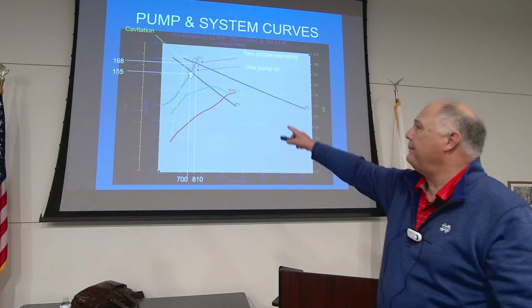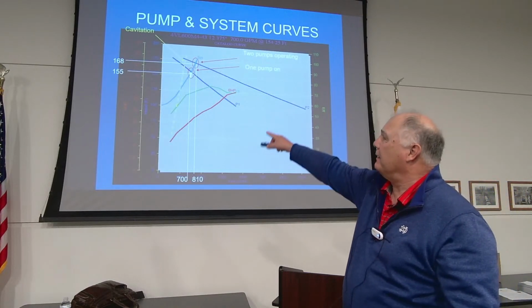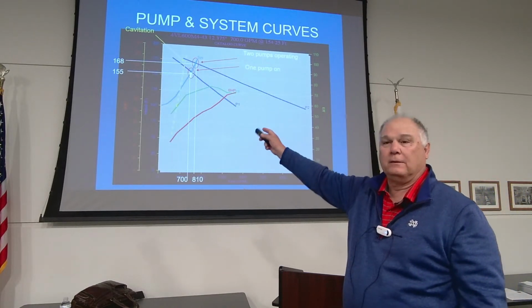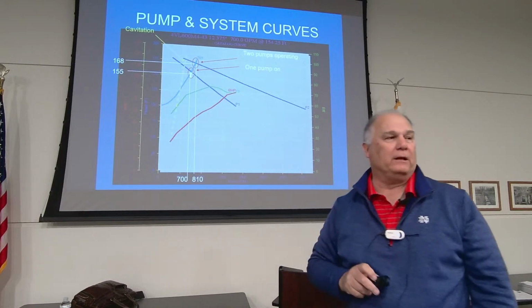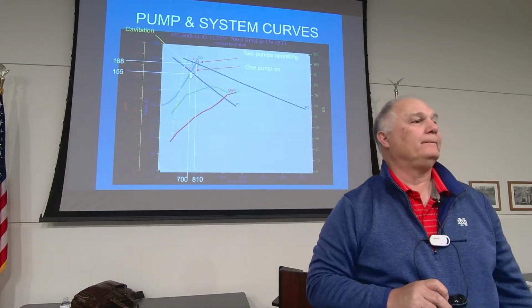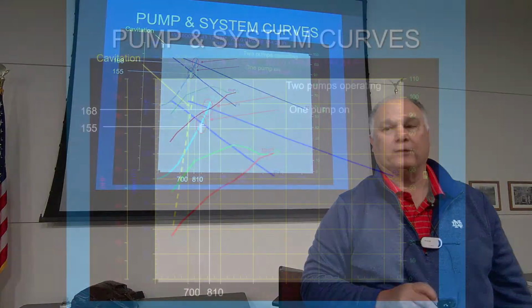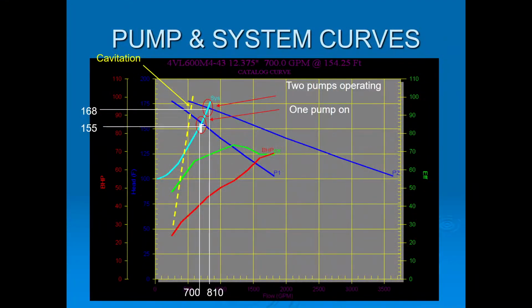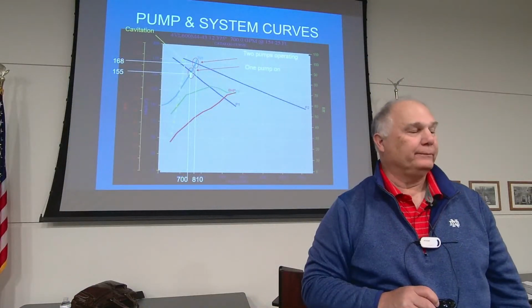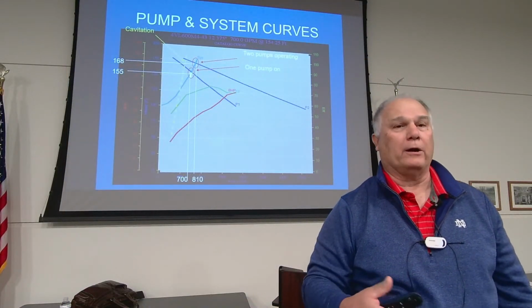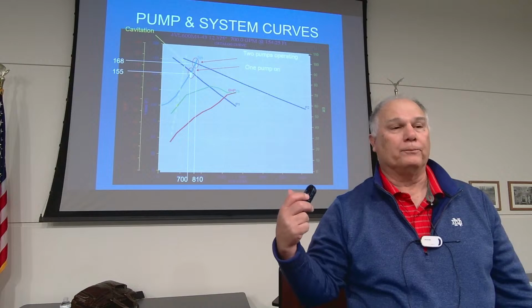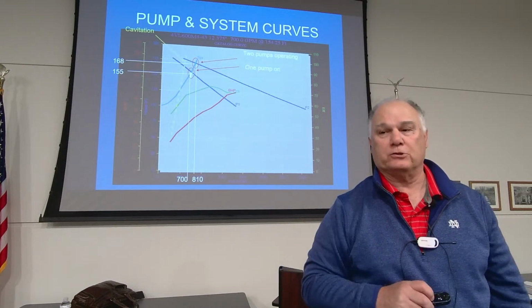We're pumping way back here to the left. See that yellow cavitation line? Each of these pumps is now cavitating. That's not a good scenario. So not only are you not pumping more through the pipe, you're destroying your pumps. Absolutely. If this condition went on and on, you'll turn your impellers into Swiss cheese.